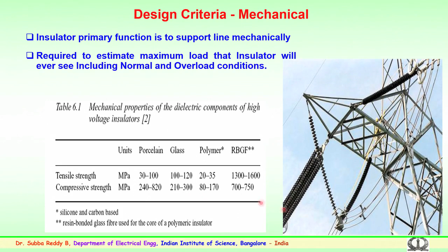So, the mechanical consideration for porcelain, ceramic or glass insulators is equally important, because when the porcelain or glass begins to crack or electrically punctures, that is the information. So, once there is a loss of insulation, the puncture could happen. Initially the surface discharge and later on because of the crack the puncture directly could happen. So, this should never exceed 50% of the mechanical and electrical rating of the insulator assembly. In case of cantilever rating, the mechanical load should not exceed more than 40%. These are the standard specified values for the insulator assemblies.